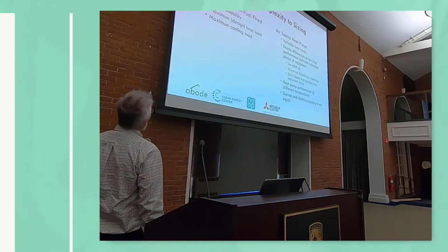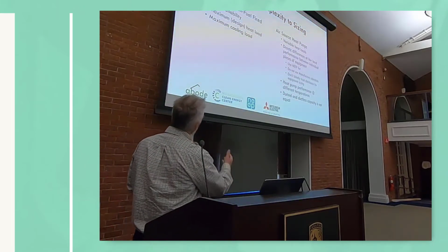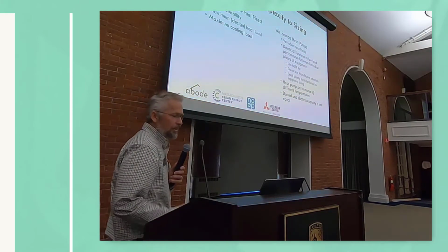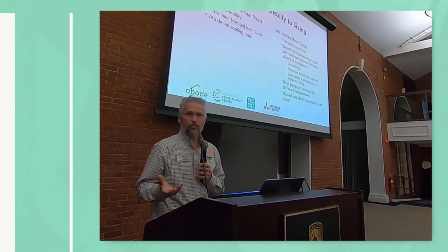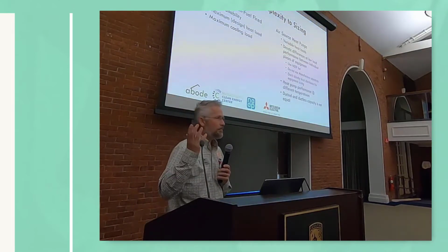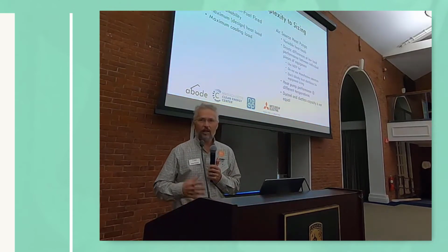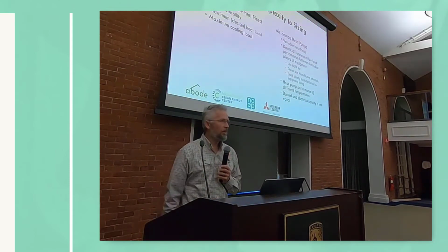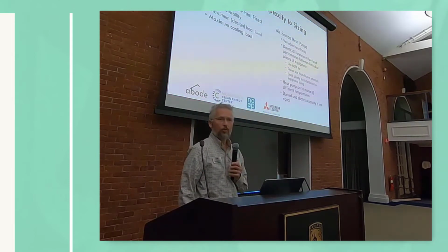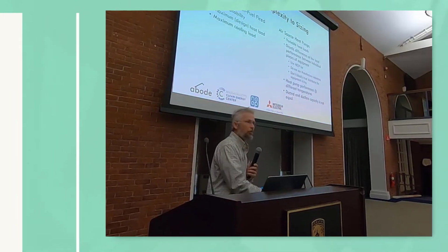So, factors associated with sizing that people talk about, this is sort of the comparison between fossil fuel-fired systems and air source heat pumps. With the conventional fossil fuel systems, HVAC guys have been oversizing systems forever. They've been going into a house, they don't necessarily do a Manual J, or they haven't necessarily done the load calculations. And they're like, well, this looks like a 100,000 BTU boiler home, or 150, or whatever they're used to installing, they'd put in these systems.